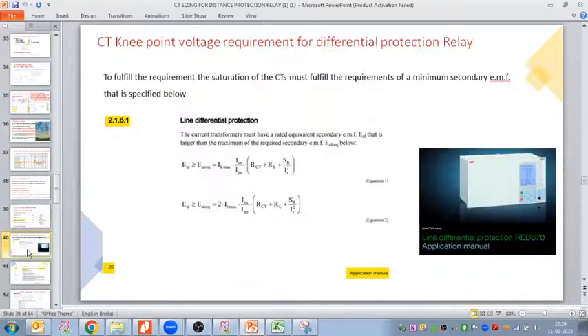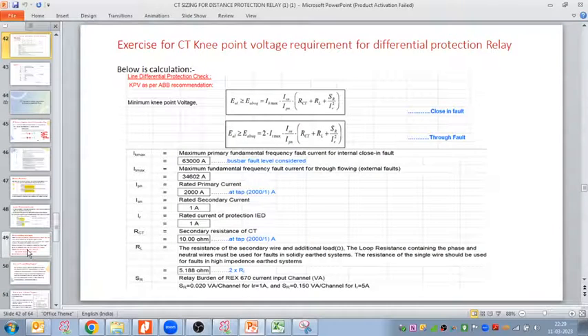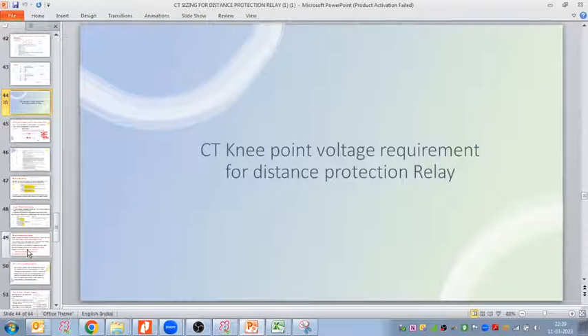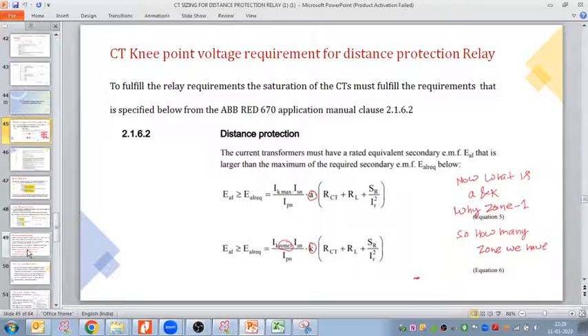Now for the CT knee point voltage requirement for the distance protection relay, first we will understand, if you see the formula, we have IK max and IK zone 1. So we will first understand about the zones, how many zones are available and which zone we have to take, and after that we will discuss the CT sizing calculations.